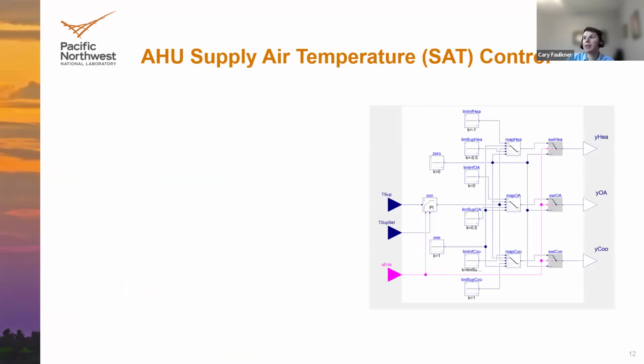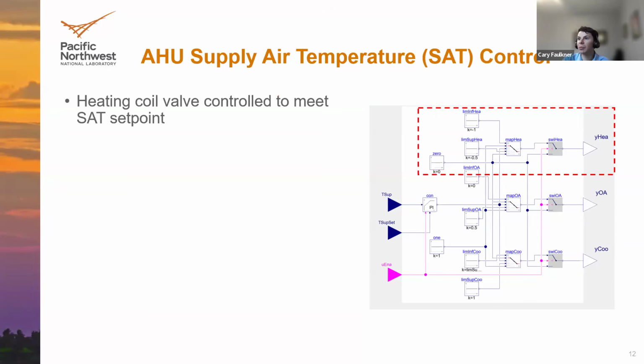And now let's talk about some of those controls at the top level of the VAV system model. So first is the supply air temperature control from the air handling unit. If we open up that block, this is what it looks like, but I'll try and break it down a little bit more. So the first aspect of the supply air temperature control is controlling the heating coil valve at the air handling unit to meet the SAT set point.